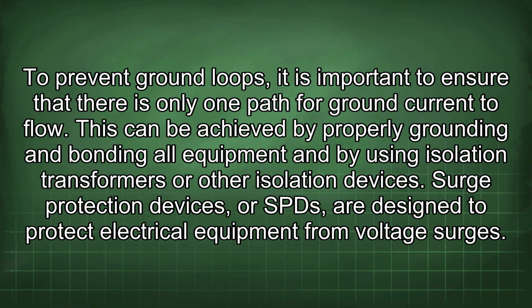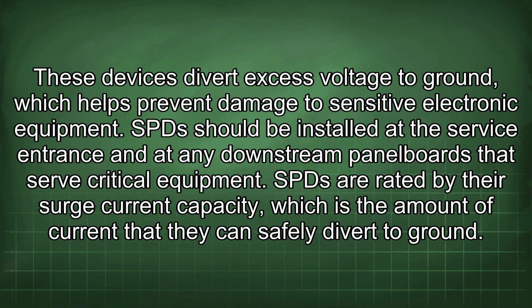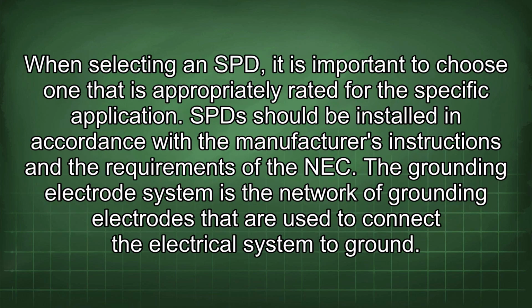Surge protection devices, or SPDs, are designed to protect electrical equipment from voltage surges. These devices divert excess voltage to ground, which helps prevent damage to sensitive electronic equipment. SPDs should be installed at the service entrance and at any downstream panelboards that serve critical equipment. SPDs are rated by their surge current capacity, which is the amount of current that they can safely divert to ground. When selecting an SPD, it is important to choose one that is appropriately rated for the specific application. SPDs should be installed in accordance with the manufacturer's instructions and the requirements of the NEC.